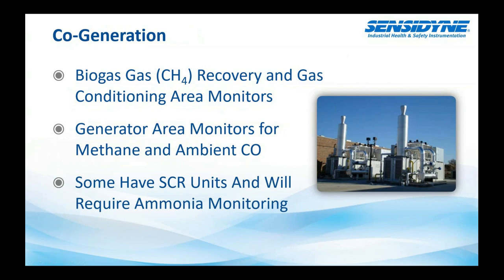Cogeneration, you're going to have biogas recovery or gas conditioning areas of monitoring. You might have an SCR, a selective catalytic reduction unit, which would be scrubbing the gas, and that would also use ammonia for that. So you would want to monitor for ammonia in these situations. You'll see a lot of these, some, not so much again in Florida. This is really big out in California, where they're capturing every bit of energy that they can and reducing emissions. They're taking that digester gas, cleaning it up, and running these generators either to produce power, or I've also seen it where they are using it to produce heat, fire boilers, things like that.